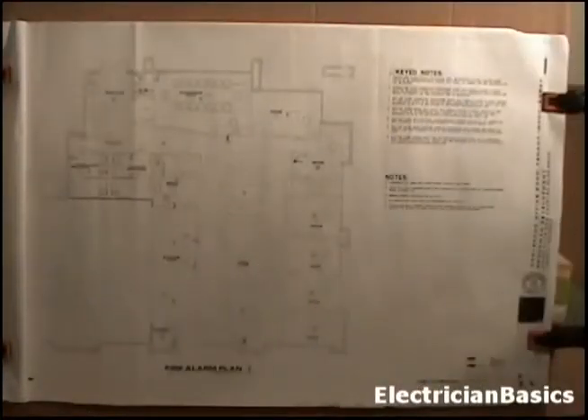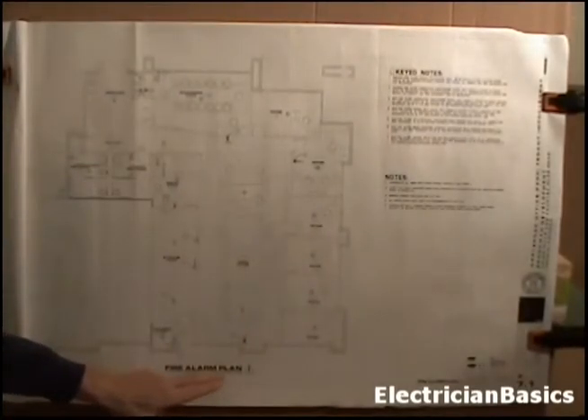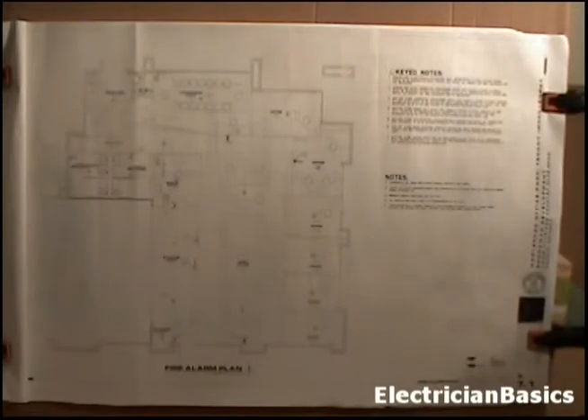The next sheet of our lesson is sheet E7.1, the fire alarm plan. And we see our scale is 1/4 inch equals a foot. I'm going to refer back to sheet E0.1. It had some fire alarm general notes on there. And the first 3 symbols for the fire alarm symbols, which was also on that same sheet, gave some mounting heights for those symbols.